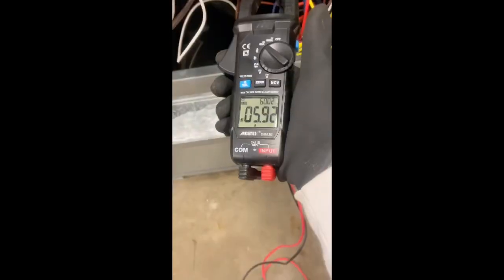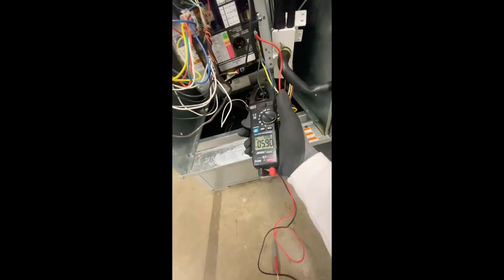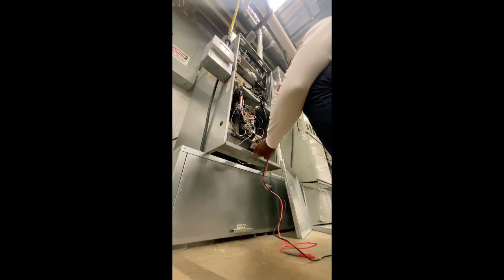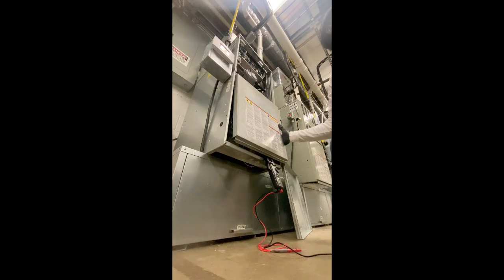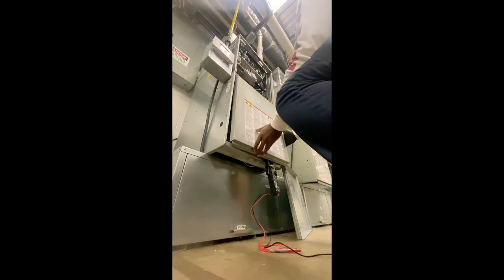So let's go to the blower motor and check if that's running the right amperage for what that motor is calling for when it's in cooling mode. And I find that it is 7.1, I believe I just saw. Yeah, sometimes these things are kind of tough to see. And let's check that cooling line. Yeah, it's a 5.93, which is only that low because the latch is open on the door. Therefore, the blower motor doesn't have to pull much air from the return box. So what I'm doing now is I'm closing this up and seeing if my amperage goes up because I'm closing that latch. And it does. And it ends up going up.